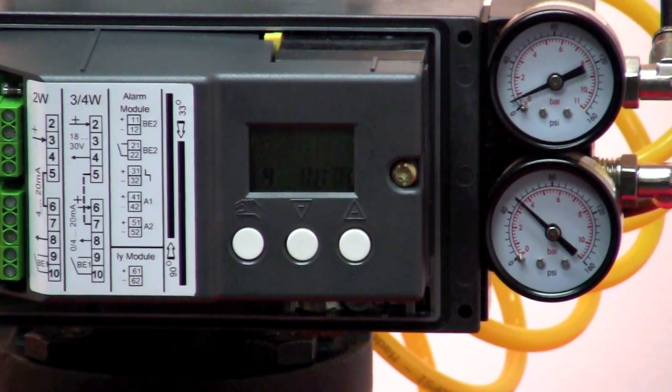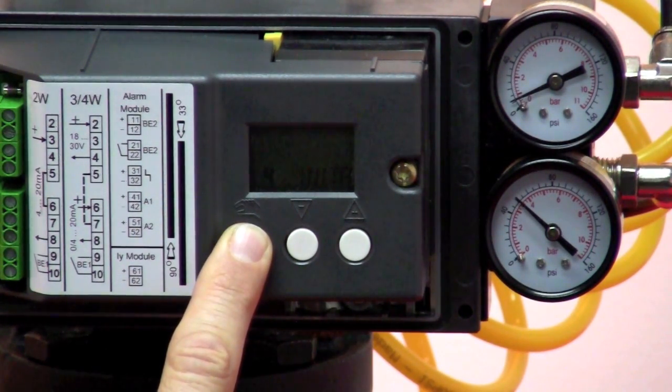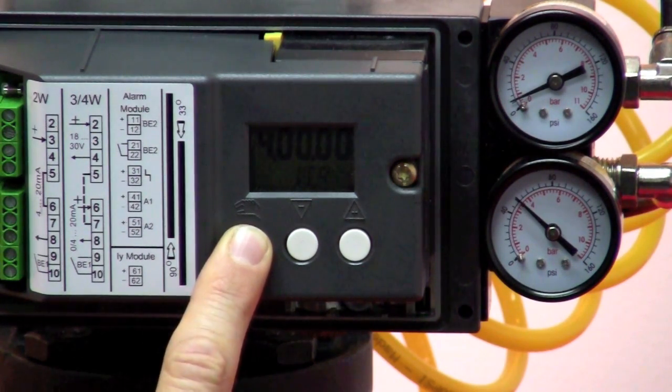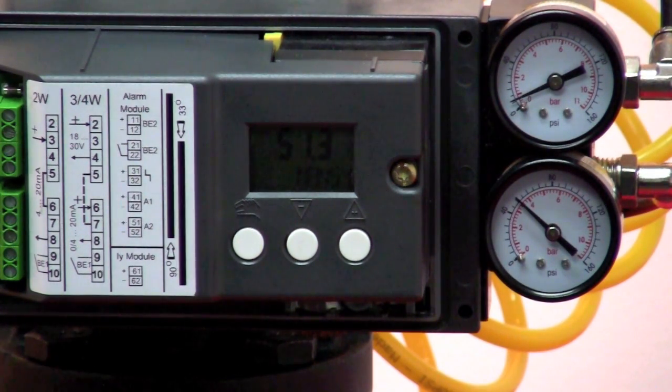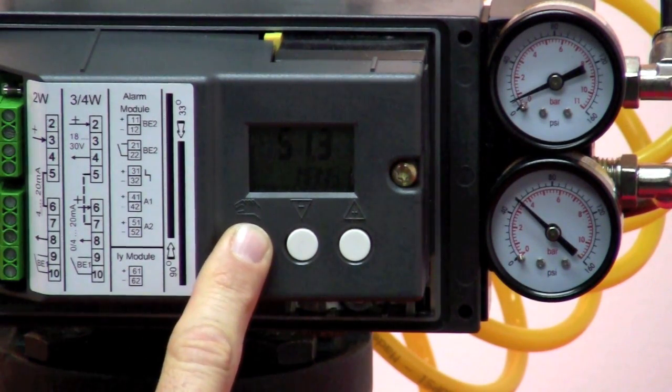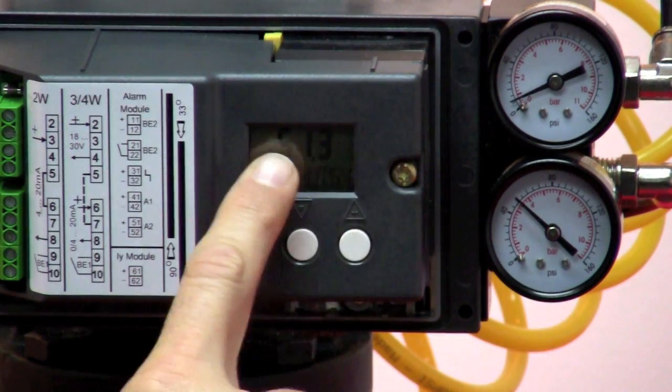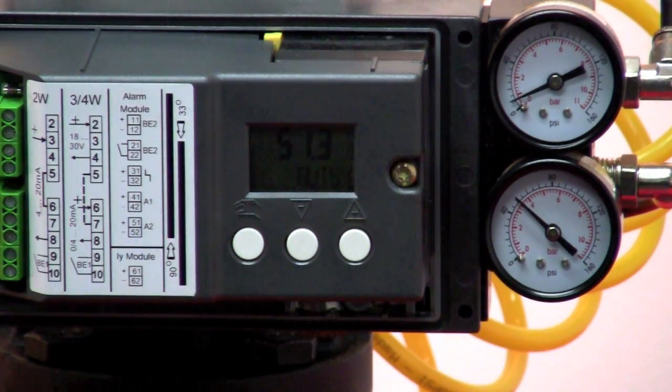Now our initialization is finished. So I exit the program mode by pressing and holding the mode key. And you can see that I emerge in manual mode. I can place the positioner in automatic mode by hitting the mode key once and you can see that my input signal is 51% and that's exactly where the positioner is now.